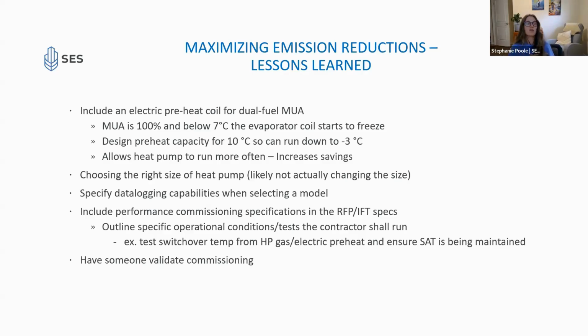So it's really important to make sure in your performance specifications, or in your RFP or request for quote, that you specify, okay, I want performance commissioning to be done. You can put in a specific list: I need you to check it at this temperature, I need you to perform these tests. You can make it very detailed, or many of the contractors we work with have documents that they use, and you can ask them for theirs and validate that it works for you. I would also recommend that you have some way to visualize that data, whether it's data logging or connecting to the BAS. I just wrote a performance spec for 4 rooftop unit replacements with a commercial client, and in the performance spec we required the rooftop unit be BACnet IP, that it had data logging, demand control ventilation, modulation, and a variable speed drive, some of those things that will ensure maximized emission reductions.